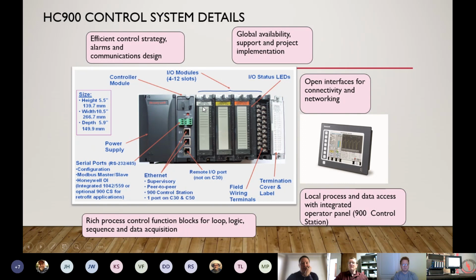You can also select several different output boards, one being an analog output board, which provides 4 to 20 milliamp output for your control loop, as well as digital out, which can be either relay, 120 volt, 24 volt, and digital inputs with either digital input contact, 120, or 24 volt. So you can get different options there for your input and output cards based on your process.